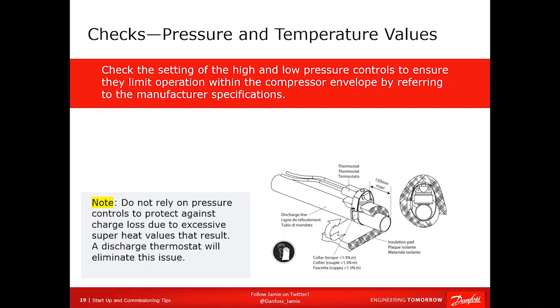And basically, they're a safety switch. They measure the discharge temperature of the gas just outside the compressor. And if it goes above a certain value, I think 260 degrees or something like that, they'll shut the compressor off. And the reason is that this is going to reflect high temperatures inside the compressor before the temperatures actually get too high inside the compressor. So it will stop and lock out the compressor, generate a service call where somebody needs to come and figure out why I'm about to burn up my compressor. So it's pretty cheap insurance for a $4,000 or $5,000 compressor. If every compressor out there had one of these on there, you could really, really reduce the amount of warranty costs and compressor failures that go on in the market.